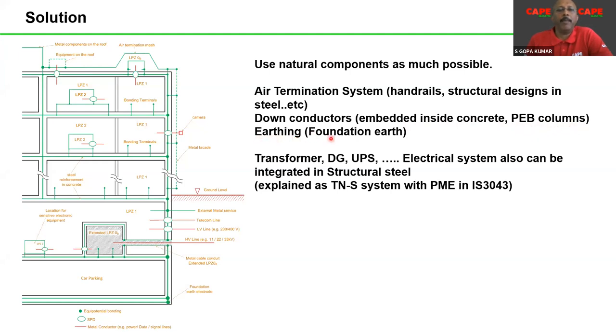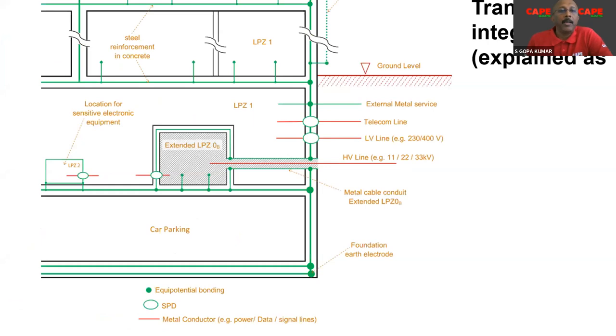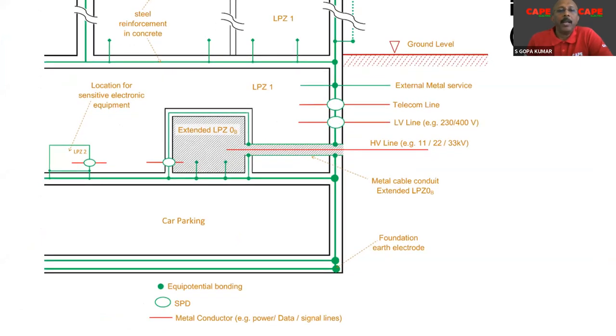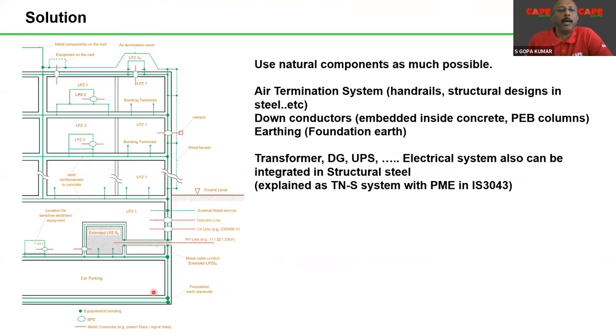Similarly, for earthing, the best method is to use the foundation earth. What is foundation earth? Here you can see, in this particular case, a building with the green color line, which is nothing but a conductor embedded inside the concrete foundation of the building. That will do your earth termination system.